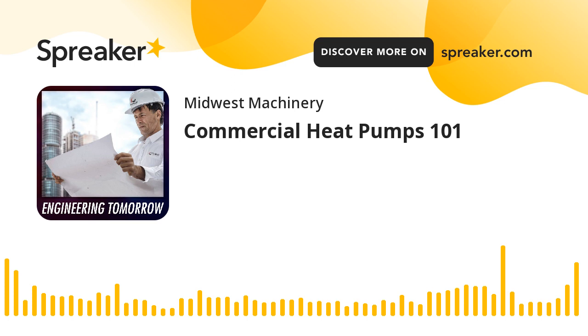Typically, from there, what we see is you take that 85 tons, which is already 85%, and you multiply that by 0.75. So what you're saying there is my cooling towers, each cell will be sized for 75% of my worst-case scenario. So it gives you a good amount of redundancy, almost 100%, but maybe call it 97% redundancy, and saves you a lot of money up front. So you're not oversizing your equipment.